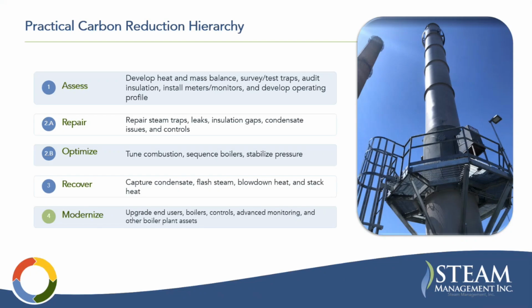So, practical carbon reduction hierarchy. First you're going to assess your system. You're going to develop a heat and mass balance, survey and test your traps, audit your insulation, install meters and monitoring for more visibility, and develop operating profiles and load cases, all the things that you can do to evaluate the performance. Then I have repair and optimize as 2A and 2B because they're both important first implementation steps. Repair steam traps, leaks, insulation gaps, condensate issues and controls, tune combustion, optimize boiler sequencing, stabilize pressure, and then look at recovery options.